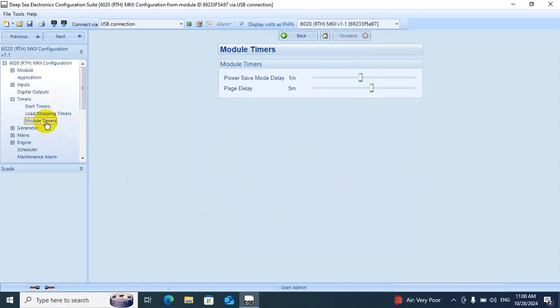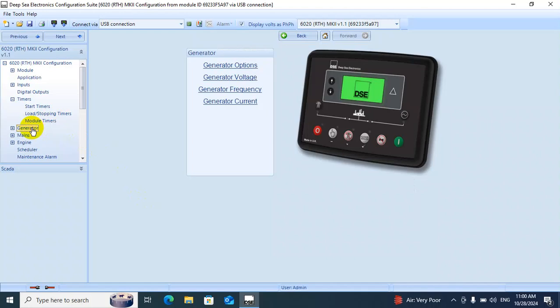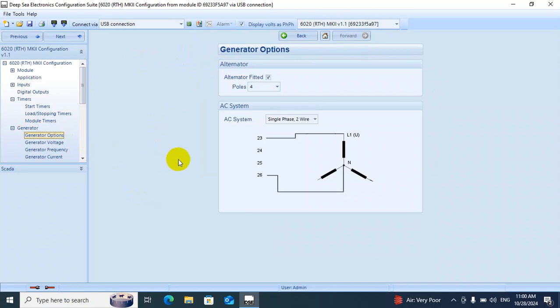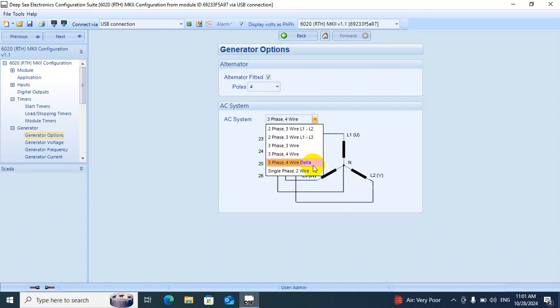For power save mode, we are coming to generator. In the generator option, the first option is about the alternator. Our alternator is 4-pole and the connection is star connection, and this program is chosen for single phase. If we want to convert the generator to 3-phase, we have to come here and select 3-phase 4-wire, like this. Now we don't need to change this. We'll bring it back to single phase.